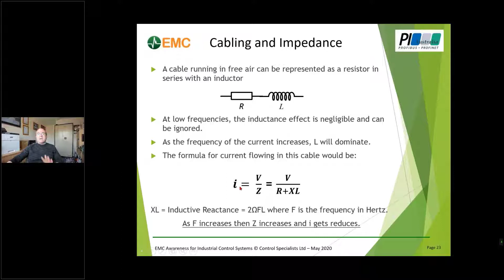If we've got two cables next to each other, conductor A and conductor B, each represented by the resistor and inductor in series, then the sheer fact that they are close to each other will mean that if we've got a changing voltage in A, the effect of capacitive coupling makes it appear as though we've got several capacitors between the two. And what we will find, if we've got, for example, 240 volts or 440 volts on A, we won't get 240 or 440 volts on B, but we will certainly get a sine wave at the same frequency. The magnitude of that will depend on a number of things, one of them being the distance between the two. So clearly we want to keep them apart.